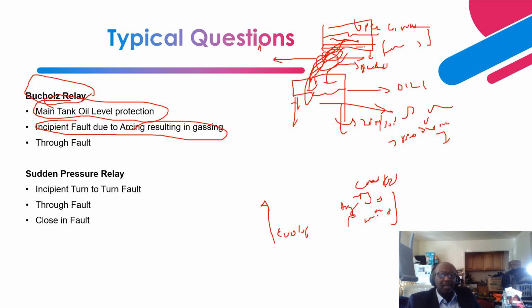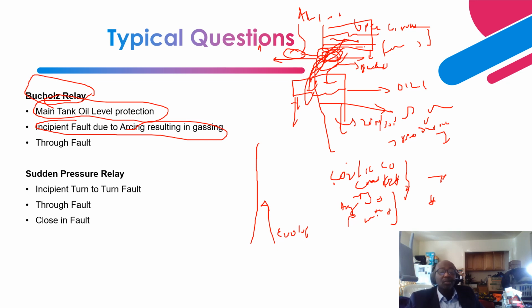Due to acetylene, and other gassing can occur due to degradation of insulation, carbon dioxide, and also heating of insulation, carbon monoxide. And also PD activity produces hydrogen. All these gases, because they are lighter than oil, rise up to the top and into a chamber inside the Buchholz. Then periodically, the volume of the gas becomes heavy, and it either alarms through a micro switch, to provide a DCS or SCADA indication of that.